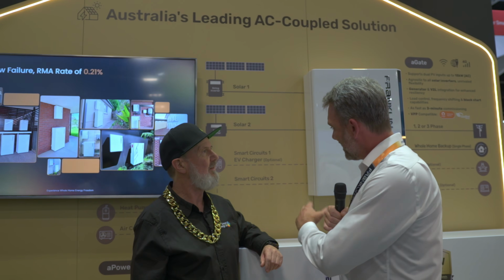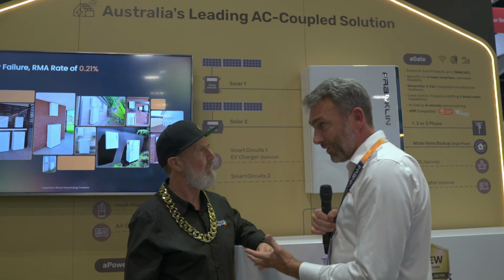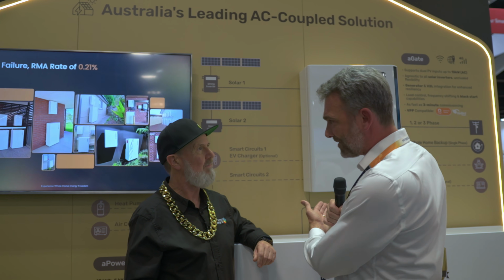Now, when I've got two of them, do I need some additional equipment? You will always need the gateway, this is only half the story. What's the gateway do? The gateway allows the whole home backup - you could call it a power router. Your grid connects in there, the battery connects, your solar connects, your backup circuits connect. And if you wish, you can have controllable loads and a generator set as well. Generator, really? So grid, battery, solar, generator, you've got everything covered there.